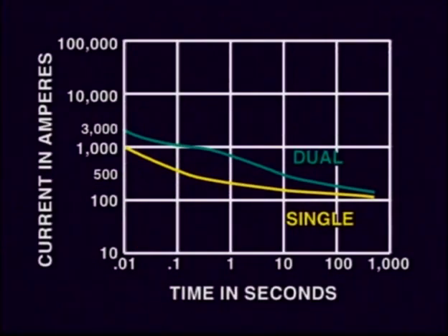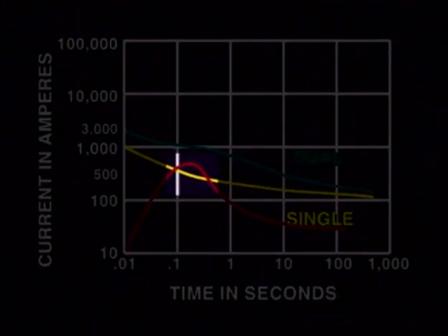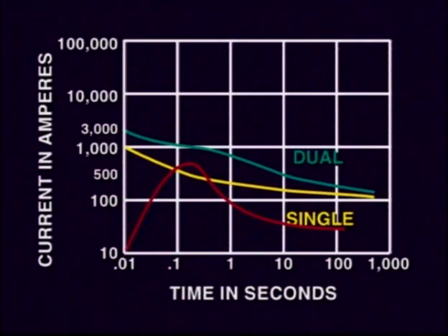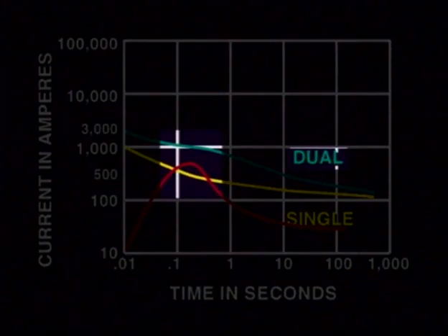You could use a non-delay fuse to protect a circuit if the motor inrush current could be sustained by the fuse during the inrush time. If the motor current passes this limit, the fuse will open. If this is the case, you may use a little larger fuse, up to 4 times the full load current according to code, instead of 3 times to protect the circuit. Otherwise, you'd be better off selecting a dual-element time delay fuse and provide adequate time for the inrush current.